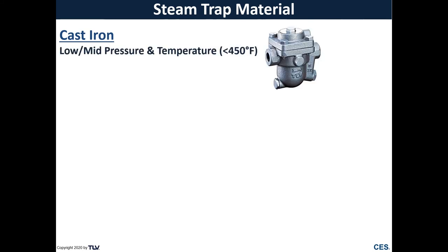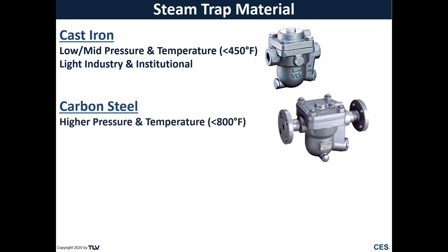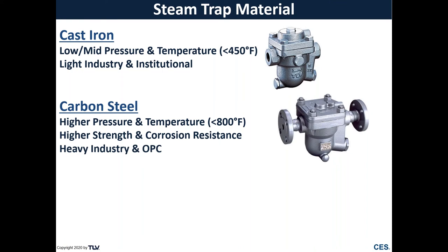Now we can take a look at steam trap material. A very common material that we see is cast iron. Cast iron is generally seen for low to medium pressures and temperatures, generally below about 450 degrees Fahrenheit. And this is very common in light industry as well as institutional type settings, such as universities or district steam distribution systems. Another is carbon steel, which is generally seen in higher pressures and temperatures, typically up to about 800 degrees Fahrenheit. And it's good for its higher strength and its corrosion resistance over cast iron. And you see this very often in heavy industry, such as the oil and petrochemical industry.